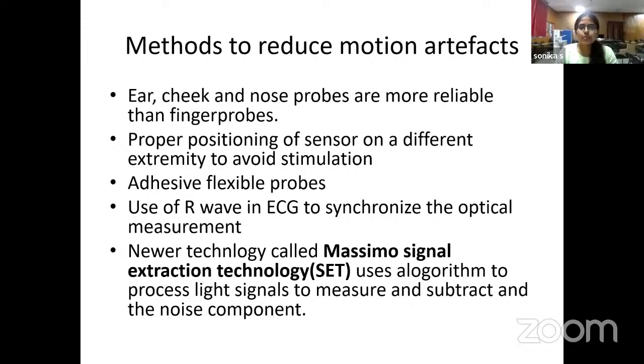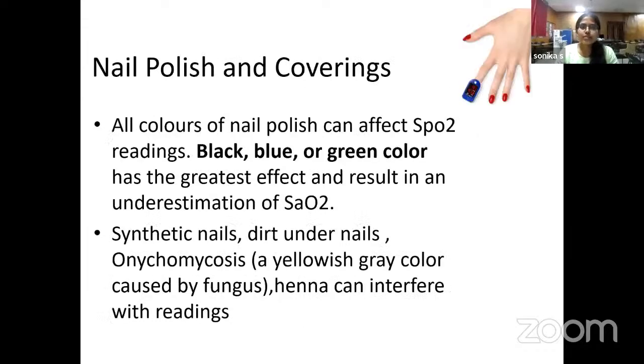And adhesive flexible probes, use of R-wave in ECG to synchronize the optical measurement, and the newer technology called Masimo Signal Extraction Technology, also known as SET, uses an algorithm to process the light signal to measure and subtract the noise component. So the next artifact is nail polish and coverings.